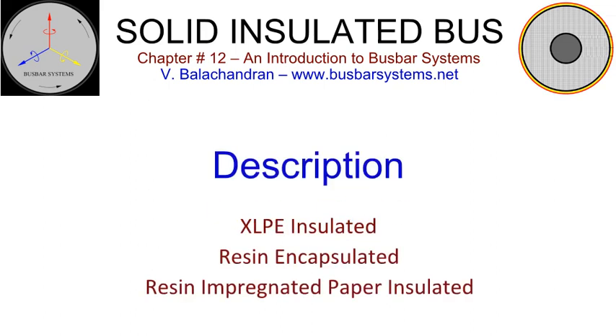Description. There are several categories of single-phase, solid insulated busbar system that can be used for a wide range of system voltage. These are classified based on the insulating material of the conductor: XLPE insulated, resin encapsulated, resin impregnated paper insulated. These are ideally suited for making connections between transformers located in outdoor switchyards and indoor panels, between indoor panels, and between equipment in switchyards. The judicious selection of solid insulated bus makes the switchyard interconnections compact.